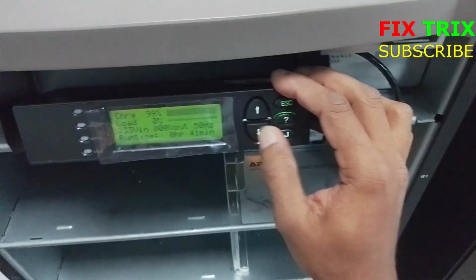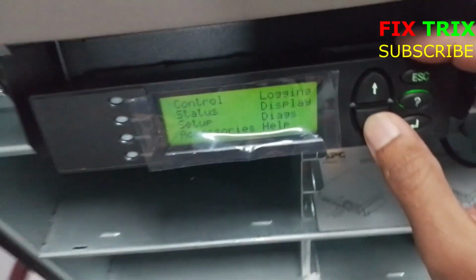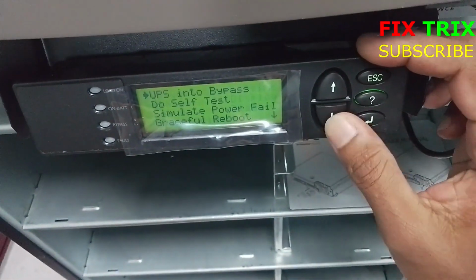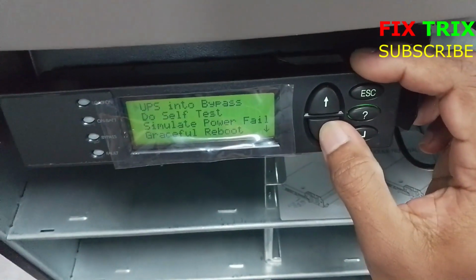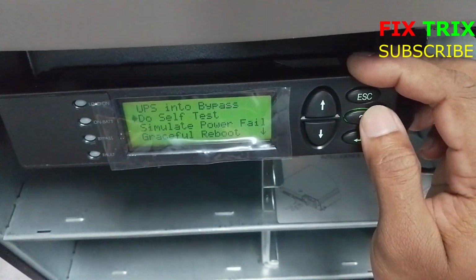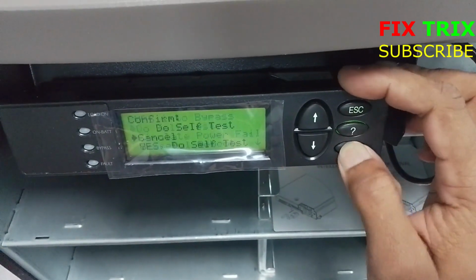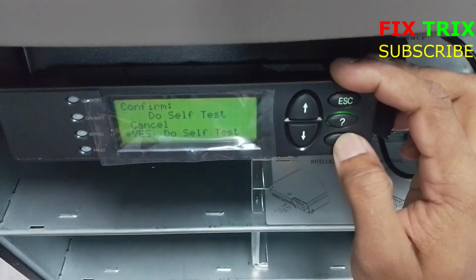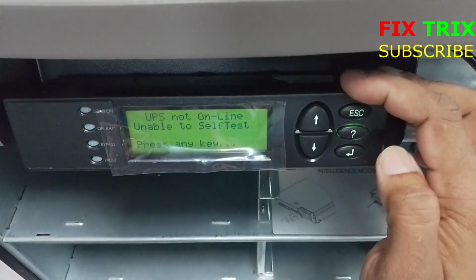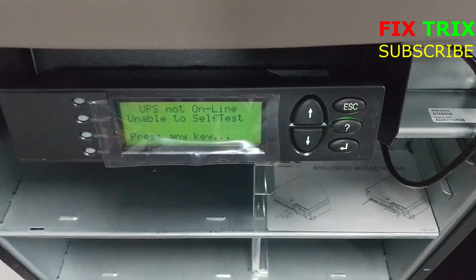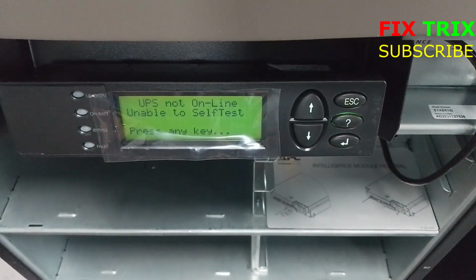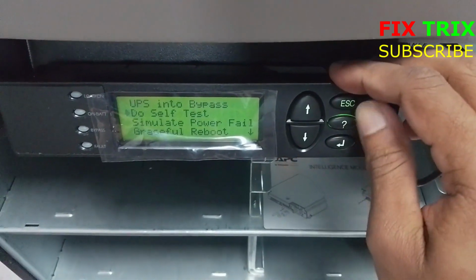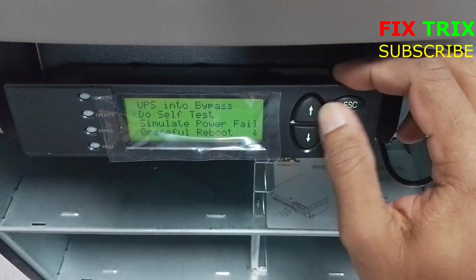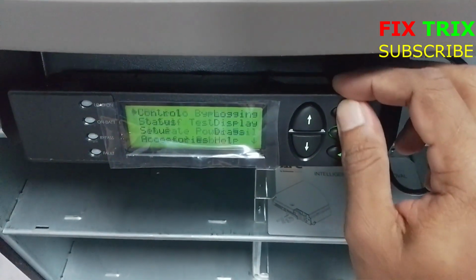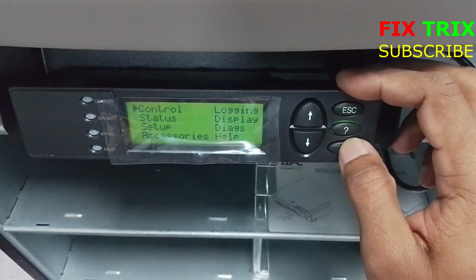Now we try to run the UPS self-test. The self-test checks power modules, battery modules, internal UPS operation. Sometimes the self-test does not start. Why this happens? Because the output load is not turned on. Some UPS systems need a minimum load to run the self-test correctly. So first we turn on the output load.